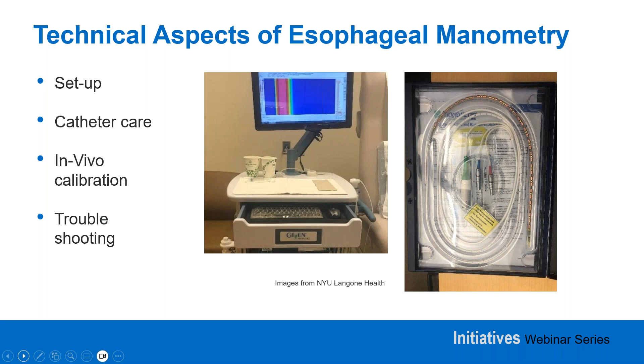The sensors on the manometry catheter are extremely delicate. We always teach our staff to handle these catheters with great care, so that they can preserve their working life and not cause consistent damage to the sensors. When we're calibrating these catheters, we do so in a vacuum chamber. Air is released inside to test the measure of the pressure on the sensors of the catheter and make sure that they're all feeling the same pressures and feeling those pressures appropriately. You can see on the monitor within the photo of our setup, there's color pressures that look like a rainbow. It's a nice straight column.